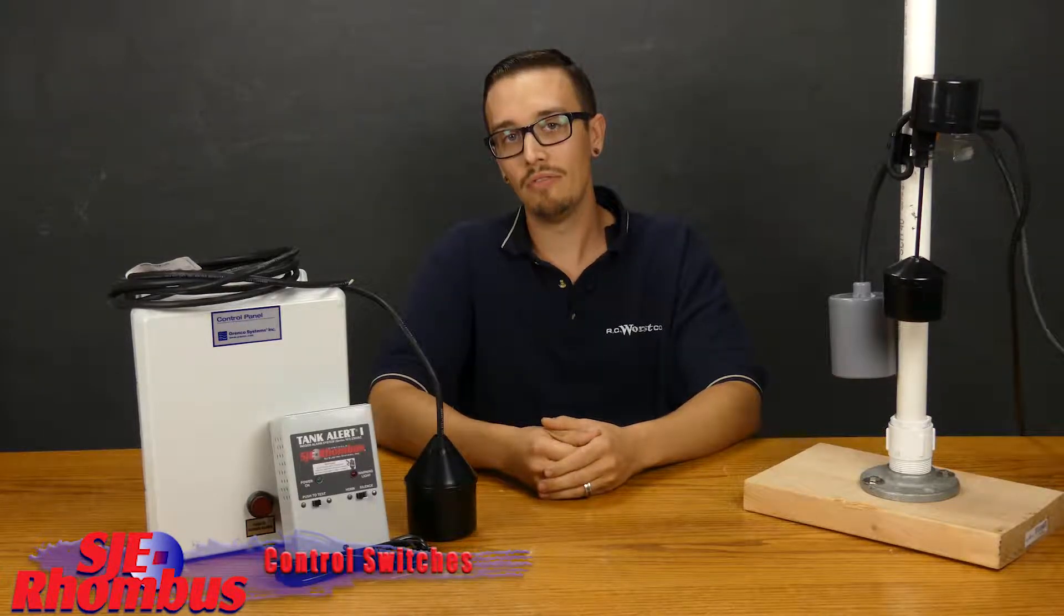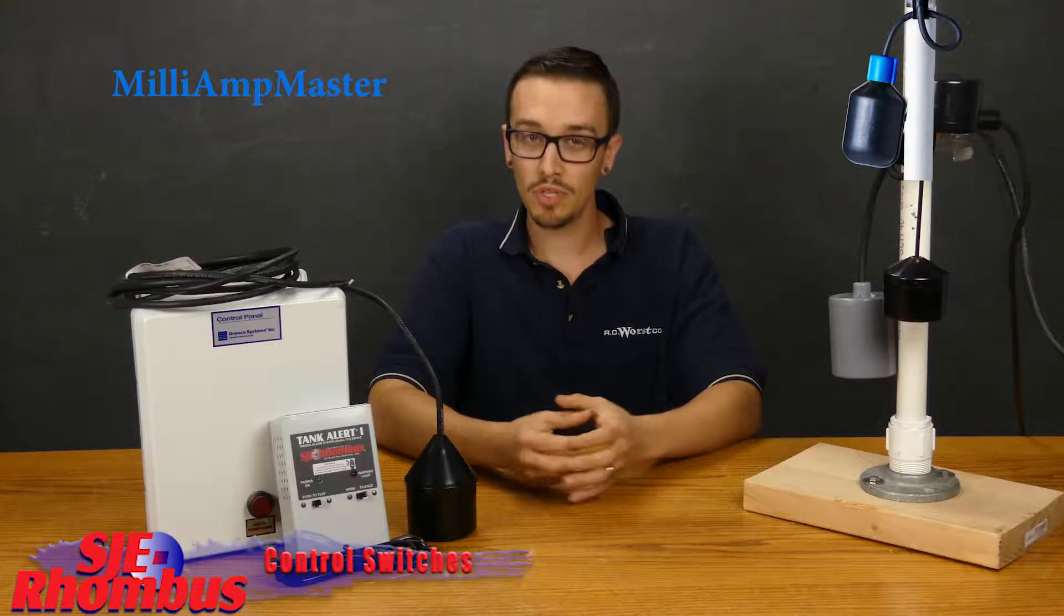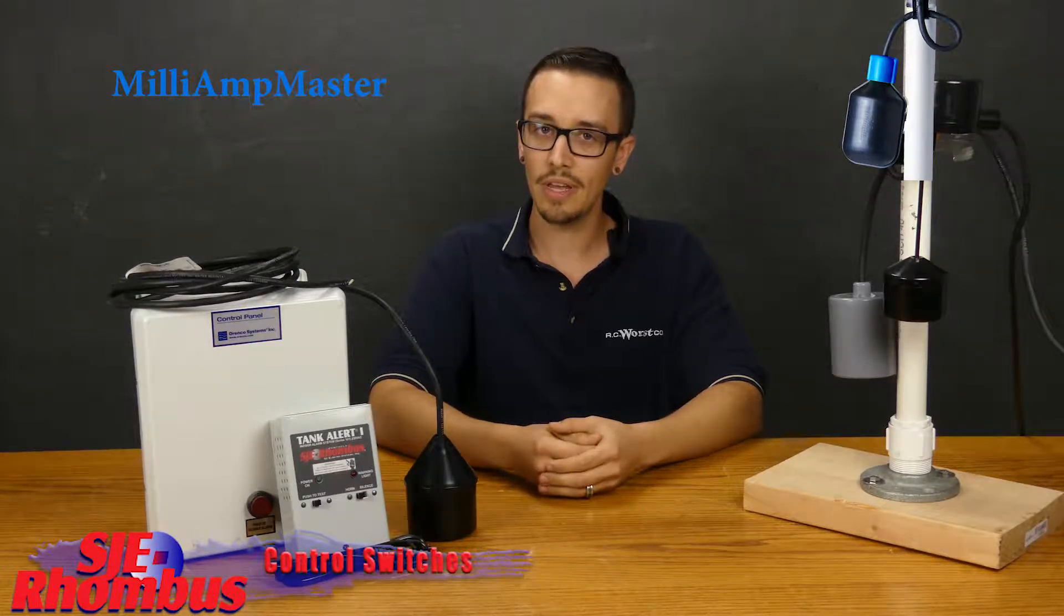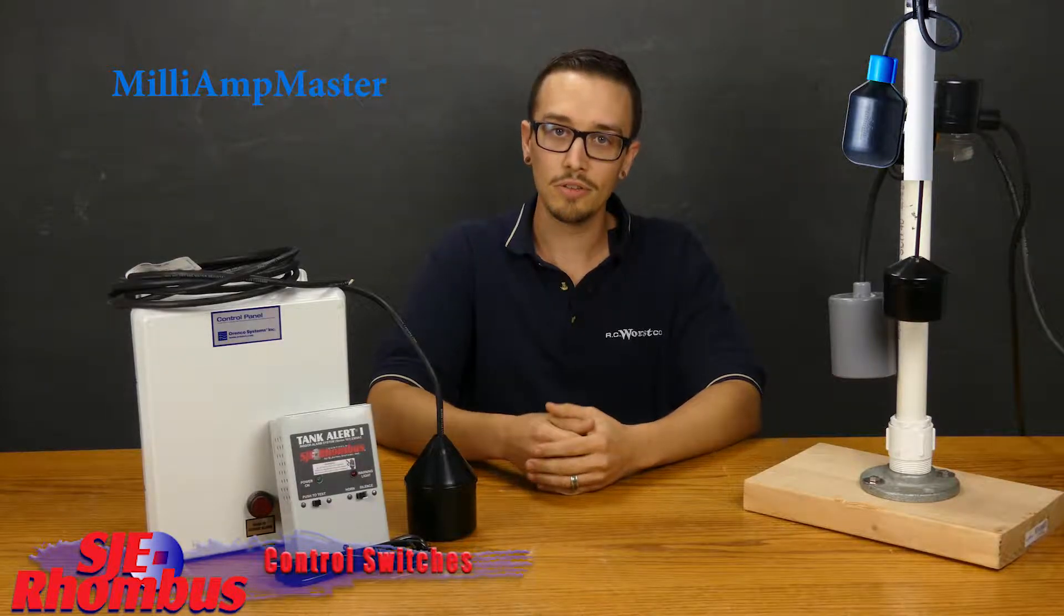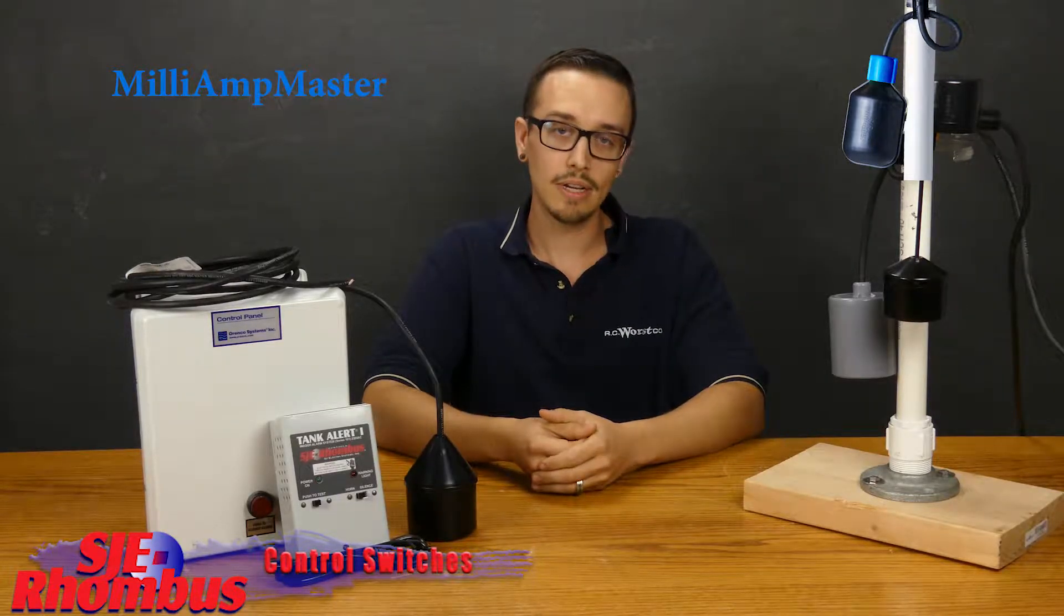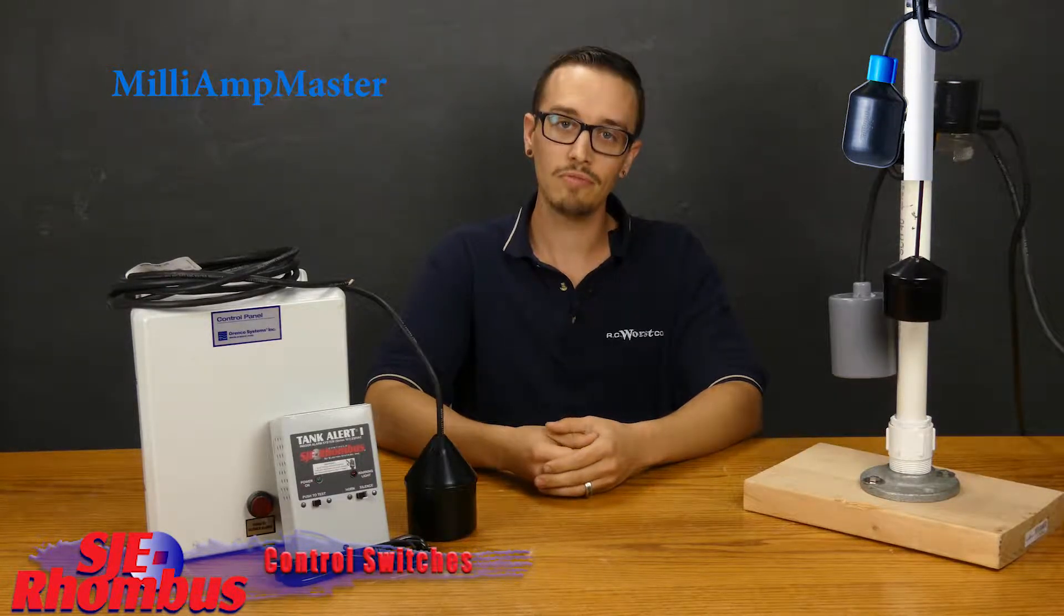In addition to that, they also have in the mechanical offering their milliamp master setup, and those are intended specifically for very low amperage applications, low voltage applications where you're dealing typically with intrinsically safe relays or explosion proof, as it's often referred to in the industry. That'd be like your class one, div one applications where you want to have a non-sparking switch, but also a switch that works well with those low voltages, and that's specifically what those are designed for.